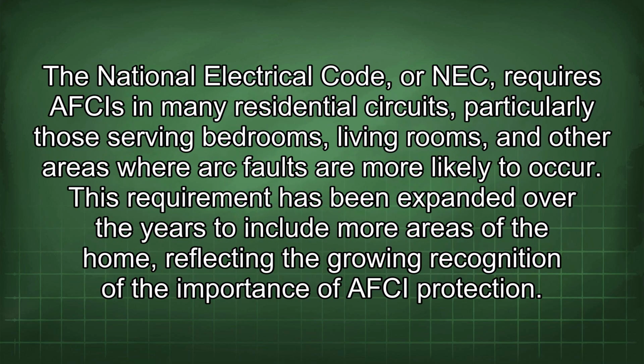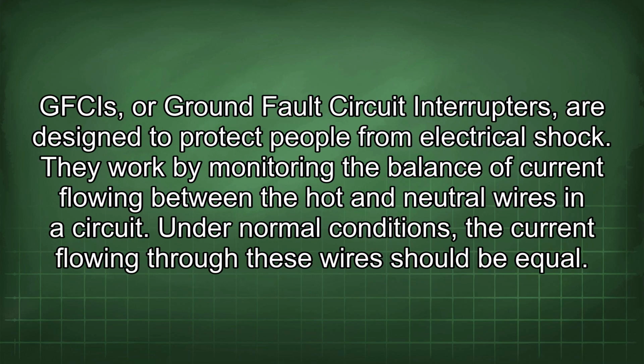The National Electrical Code, or NEC, requires AFCIs in many residential circuits, particularly those serving bedrooms, living rooms, and other areas where arc faults are more likely to occur. This requirement has been expanded over the years to include more areas of the home, reflecting the growing recognition of the importance of AFCI protection. GFCIs, or ground fault circuit interrupters, are designed to protect people from electrical shock. They work by monitoring the balance of current flowing between the hot and neutral wires in a circuit. Under normal conditions, the current flowing through these wires should be equal.